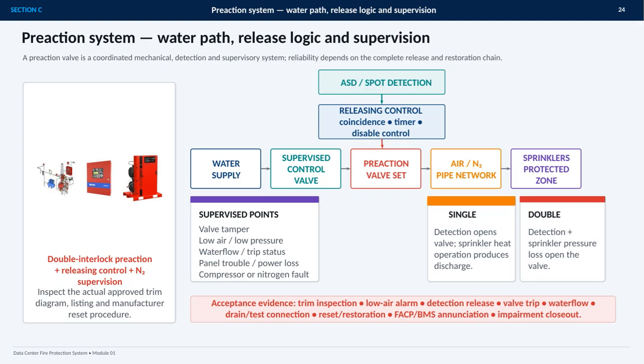Water is held back at the supervised control valve and preaction valve set, while the downstream pipe network is supervised with air or nitrogen. In a double interlock arrangement, the releasing control must receive the required detection signal and confirm sprinkler side pressure loss before the valve opens. The releasing logic may include coincidence, a timer, and a disable control. This is different from a single interlock system, where detection alone opens the valve and sprinkler operation then produces discharge.